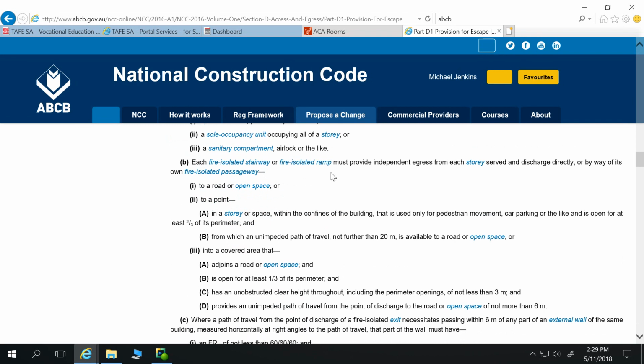Each fire isolated stairway or fire isolated ramp must provide independent egress from each story served and discharged directly or by way of its own fire isolated passageway to a road or open space, or to a point in a story or space within the confines of a building that is used only for pedestrian movement, car parking or the like, and is open for at least 2/3 of its perimeter. That means that at the base of your fire isolated stairways, you have to open out to the outside. We can't be terminating our stairway inside that bottom floor and then having to go to the car showroom or something like that, or whatever you're using that showroom for. So I'd say yeah. So story served and discharged directly or by way of its own fire isolated passageway to a road or open space.